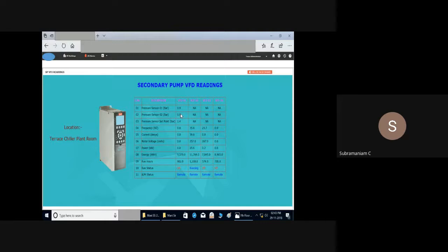So what will happen? The PLC will start reducing the VFD speed. You have to see whether it is happening even over 5 minutes, 10 minutes, 15 minutes. If that does not happen, we have to call that secondary pump PLC vendor and ask him to check his programming. And most often, when we commission and hand over the building, it will not be 100% occupied. And at that time, if they commission, the set point values will be different. So what we need to do, after the 100% occupancy of the building is there, is revisit all this set point commissioning, and we have to do recommissioning of the building.